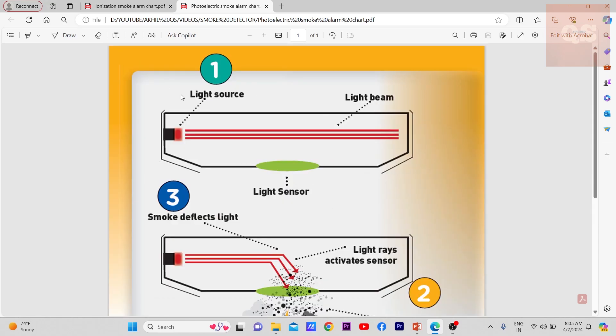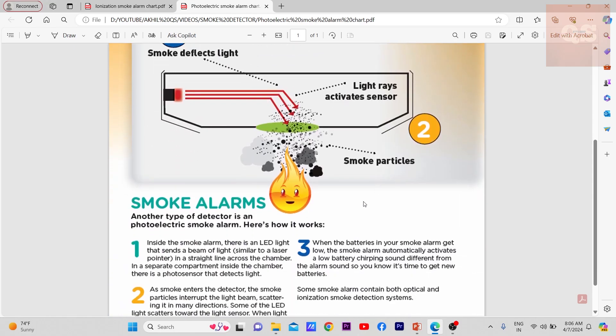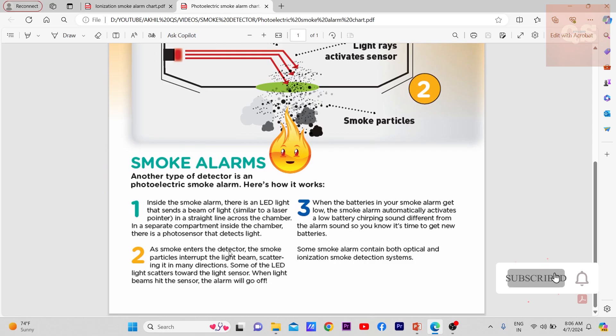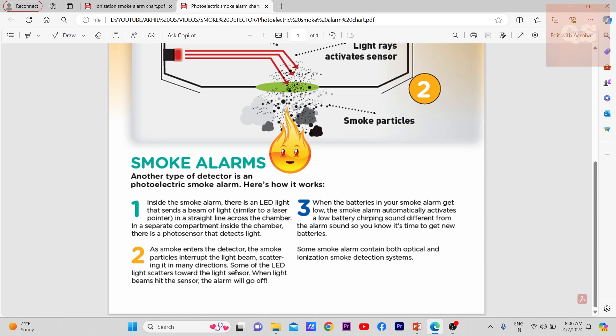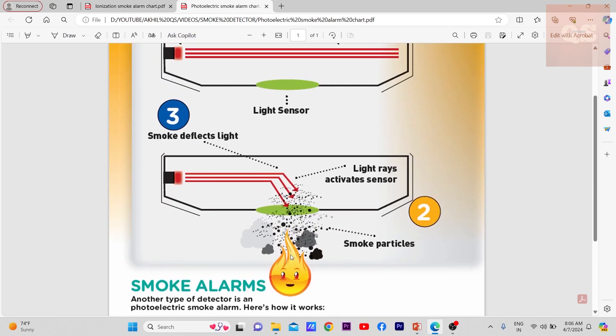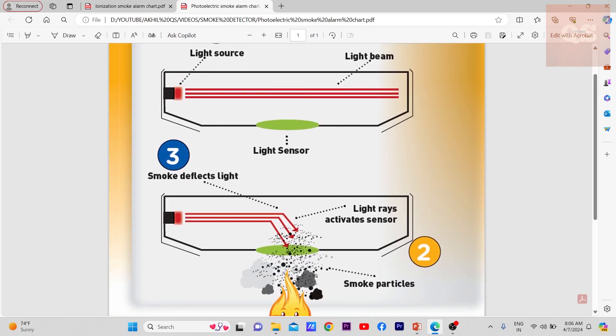As smoke enters the detector, the smoke particles interrupt the light beam, scattering it in many directions. Some of the LED light scatters towards the light sensor. When light beams hit the sensor, the alarm will go off. When the fire breaks, the smoke contains small particles that will cause this straight line of emission to break, and some light will fall into the sensor, causing the alarm to go off.